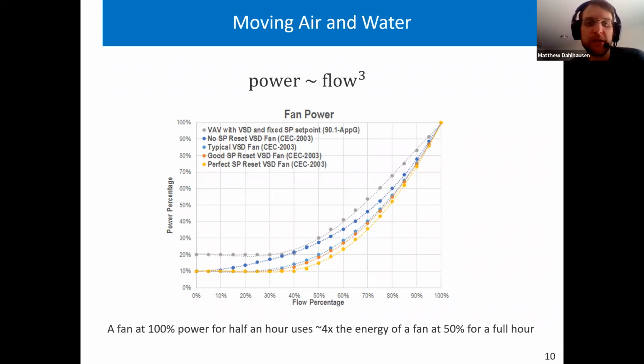In our example, we use energy in 4 ways: sensible cooling, latent cooling, sensible reheating, and the energy associated with moving the air. And it's a lot of air mass to move. We ventilate enough in typical commercial buildings to replace all the air in a room every 1 to 2 hours. The power it takes to move air with a fan or water with a pump is proportional to the cube of the flow rate.